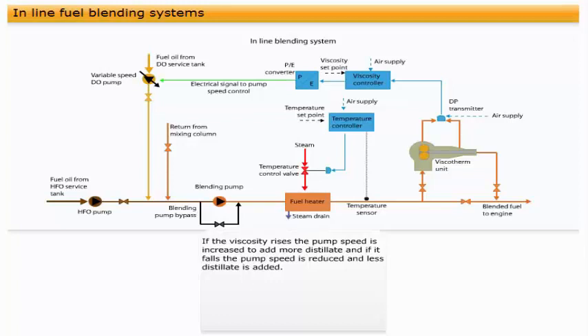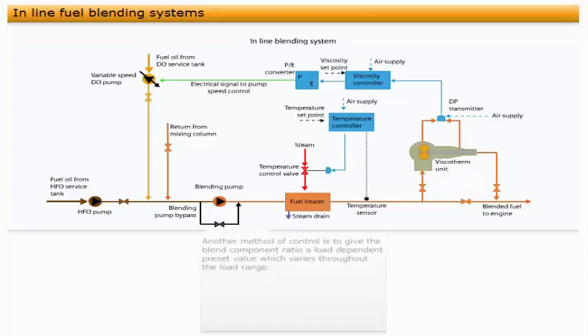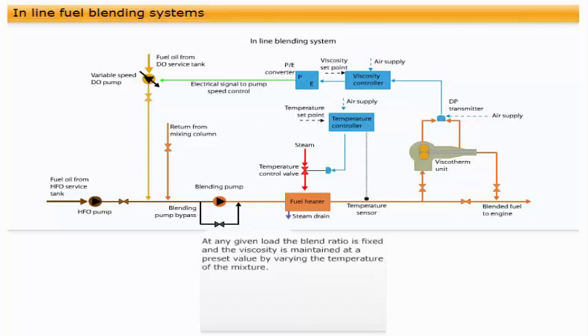If the viscosity rises, the pump speed is increased to add more distillate, and if it falls, the pump speed is reduced and less distillate is added. Another method of control is to give the blend component ratio a load-dependent preset value, which varies throughout the load range.